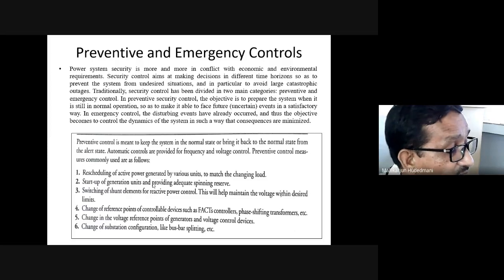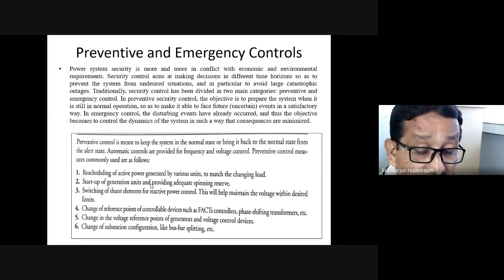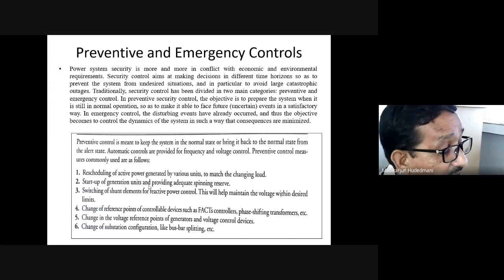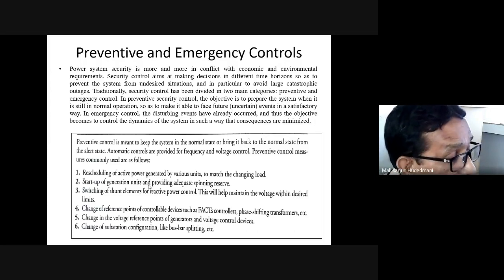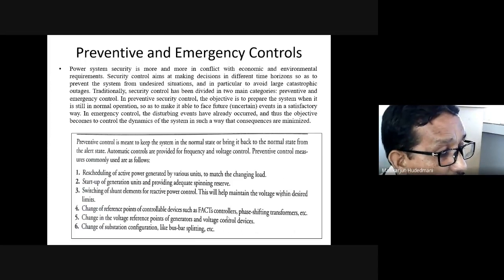As we are very much aware, there is a direct connectivity between active power and frequency, reactive power and the voltage. Anything which the voltage you are not able to maintain is an indicator that reactive power in the system is insufficient. Reactive power cannot be generated like active power and transmitted over a long distance. There is a demerit of that. It must be suitably worked out at the point of requirement.